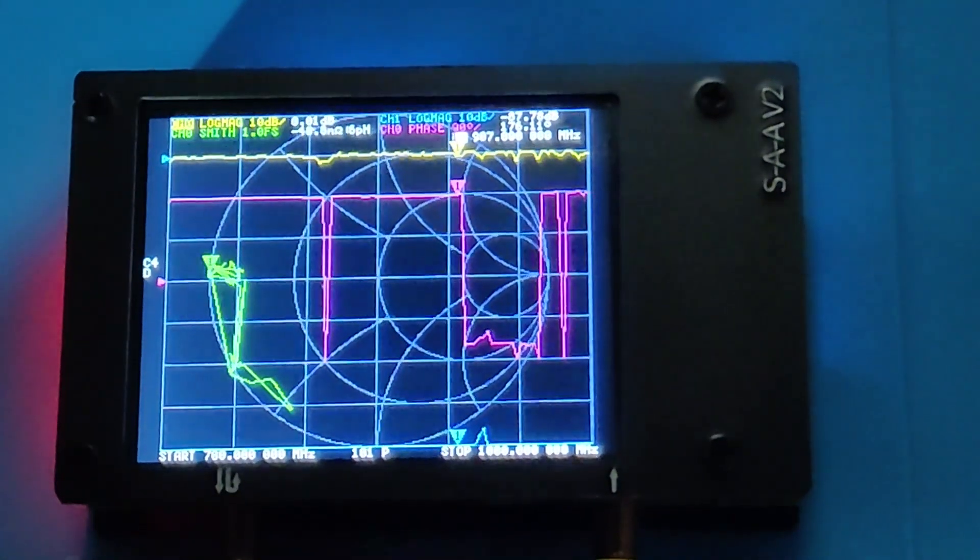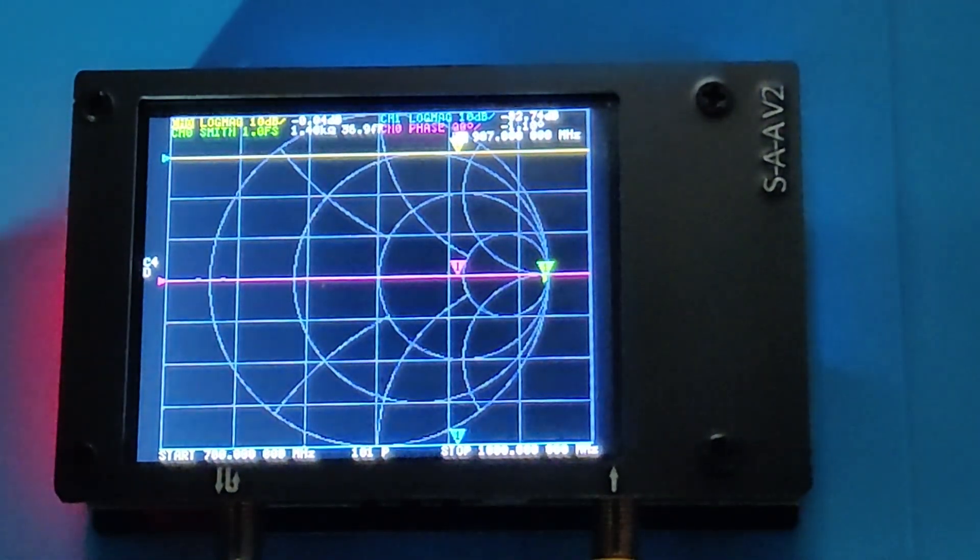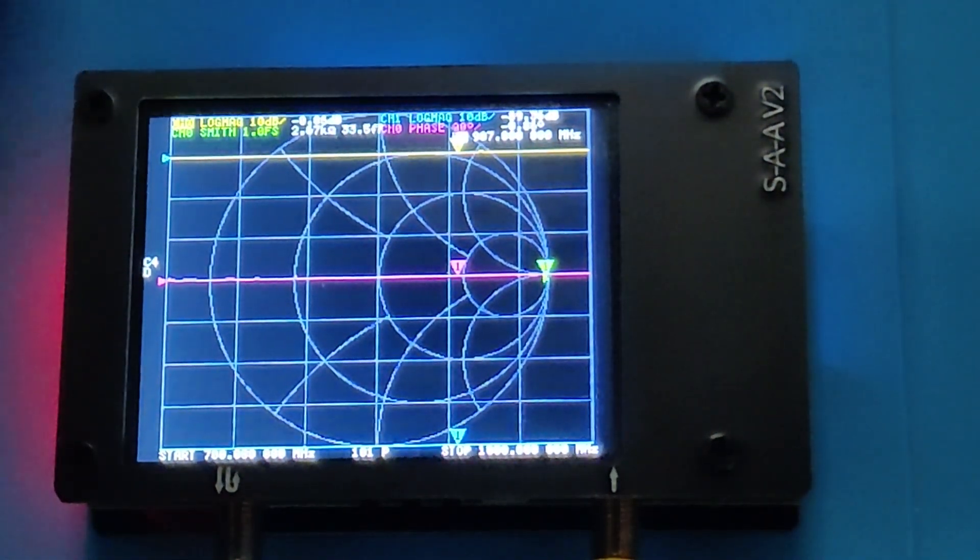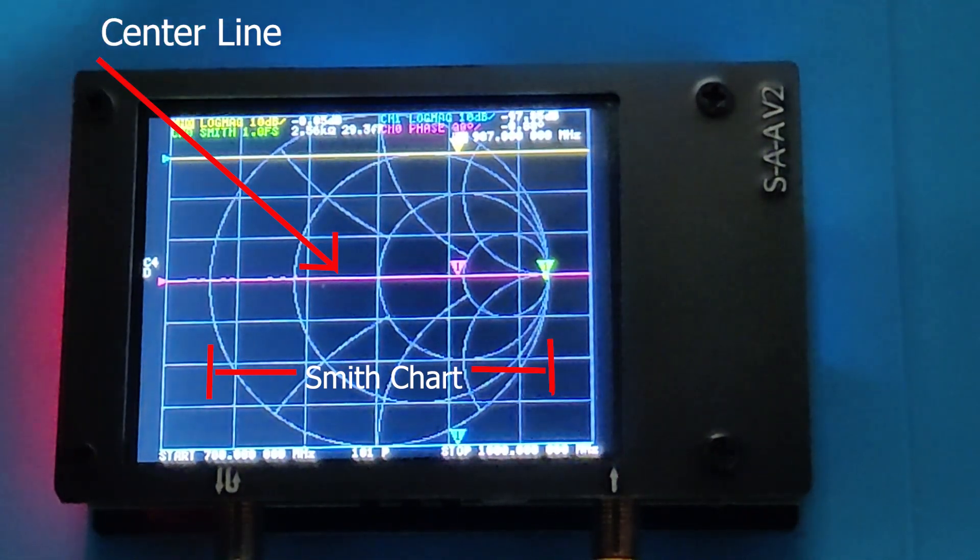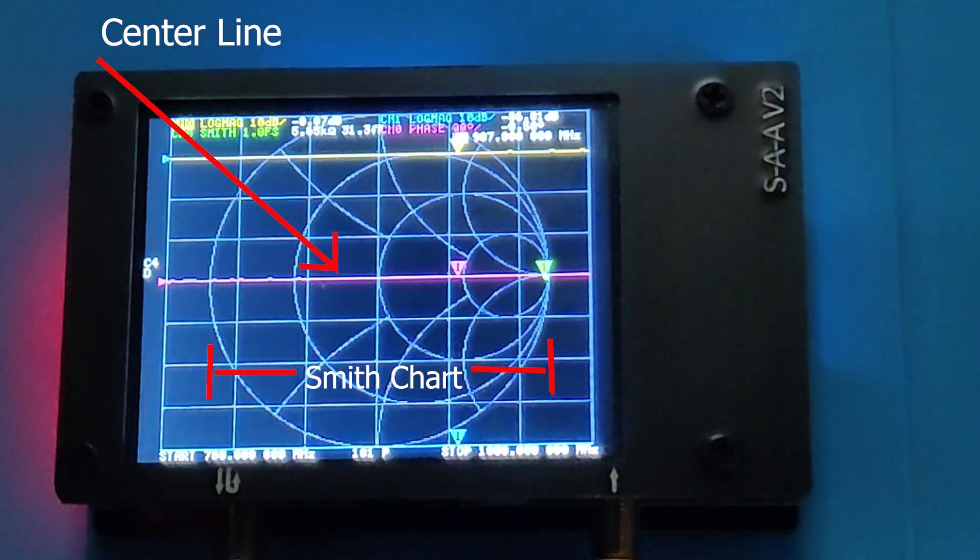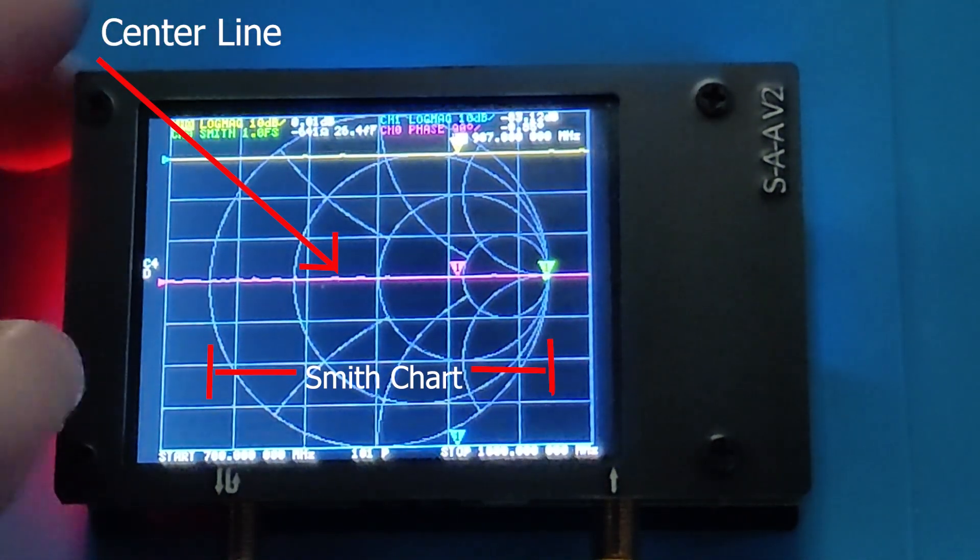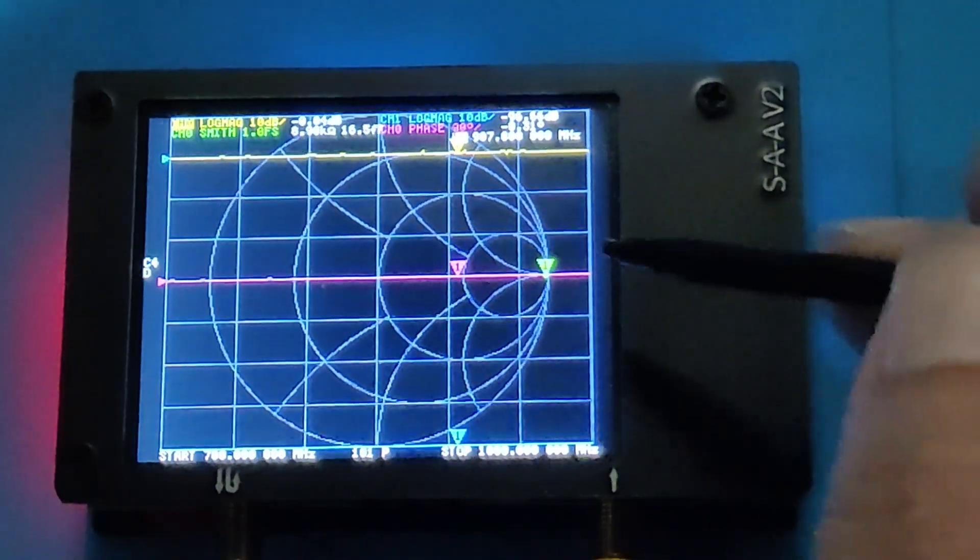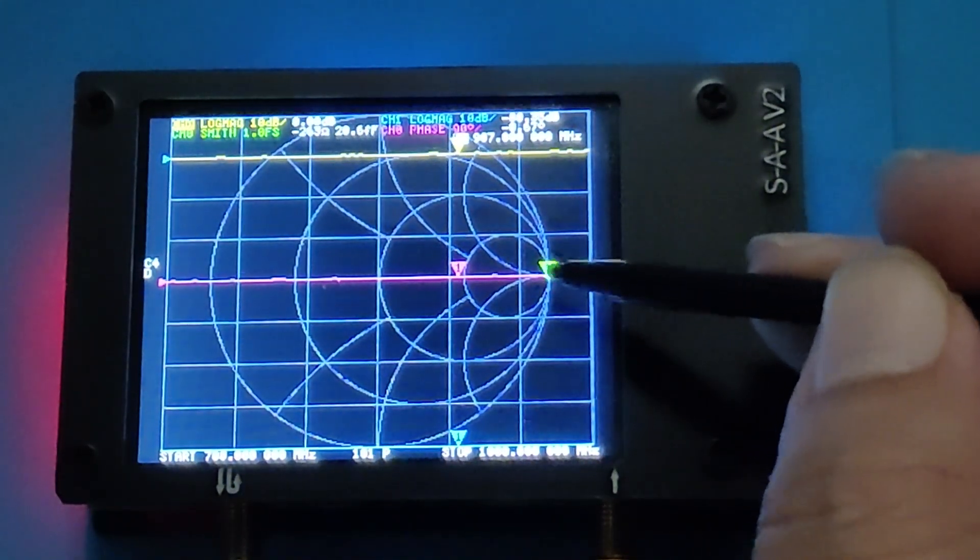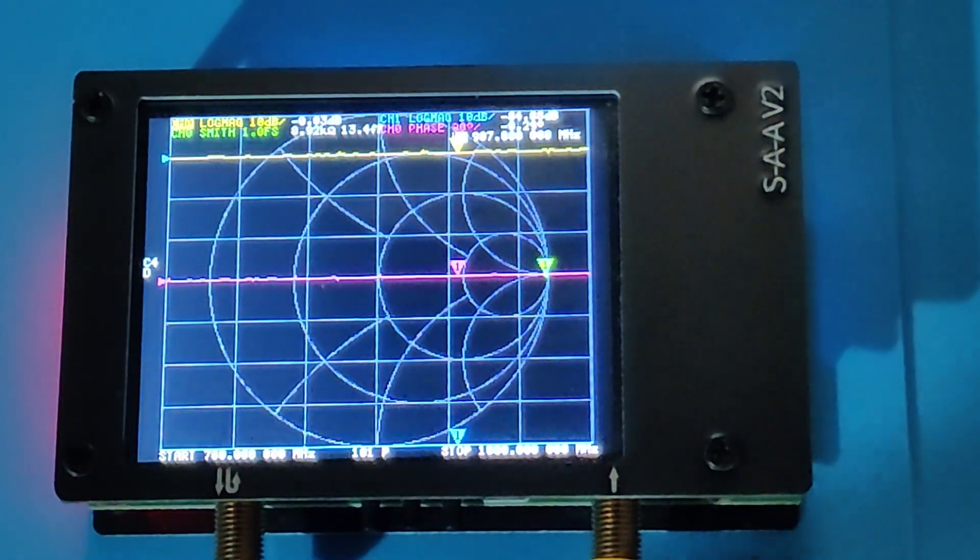Now I have replaced it with the open reference load, and this is the rightmost point on the Smith chart, centered right, to represent that we have an open circuit. So it verifies our calibration. See you again in the next part for S21 calibration.